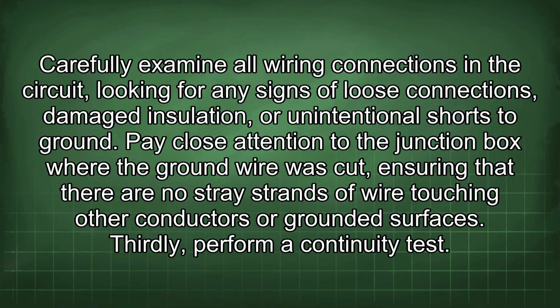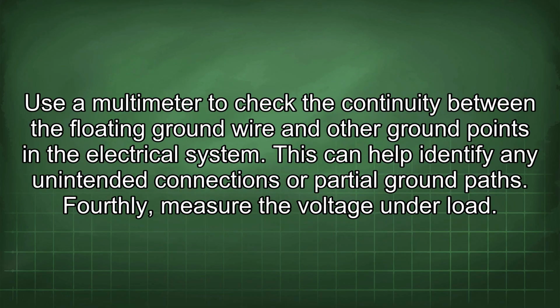Thirdly, perform a continuity test. Use a multimeter to check the continuity between the floating ground wire and other ground points in the electrical system. This can help identify any unintended connections or partial ground paths.